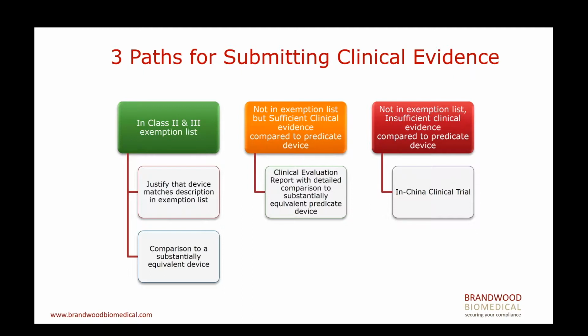Firstly, in the one on the left in green here, if your device is either Class 2 or 3, but it's in an exemption list, then you have to do two things. You have to actually explicitly document in the regulatory filing that your device matches the description of one of the devices in the exemption list. In other words, that you truly are an exempt device. And you still have to include a comparison to a substantially equivalent device that's already approved in China. So that still has to be done, although that comparison is very straightforward. And we'll look at that in a moment.